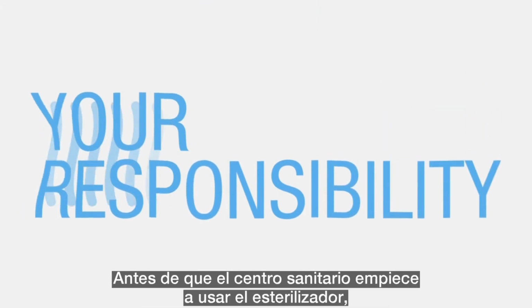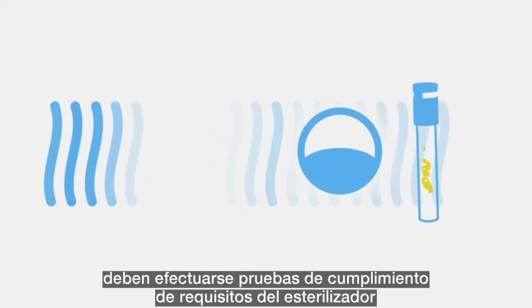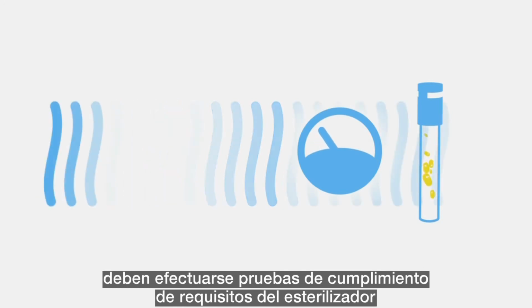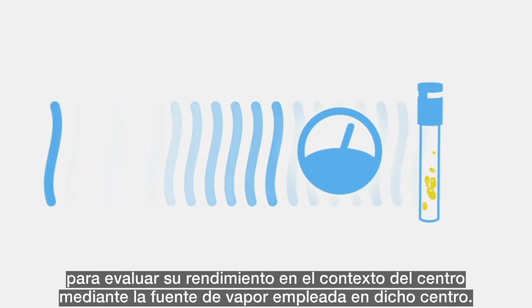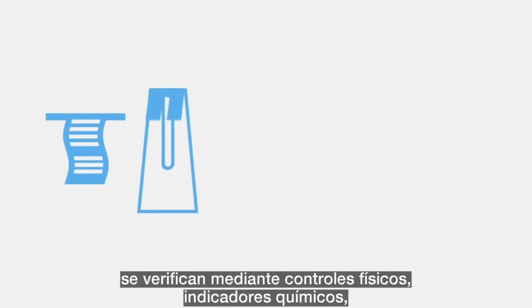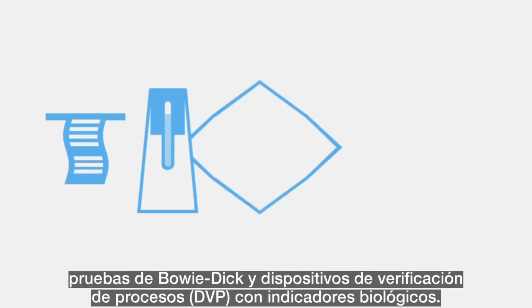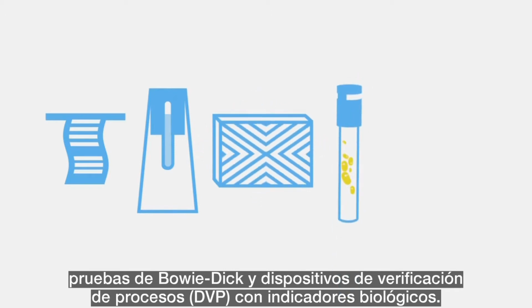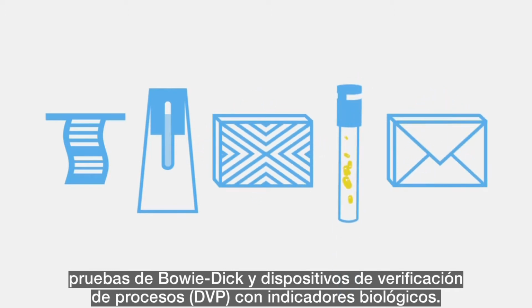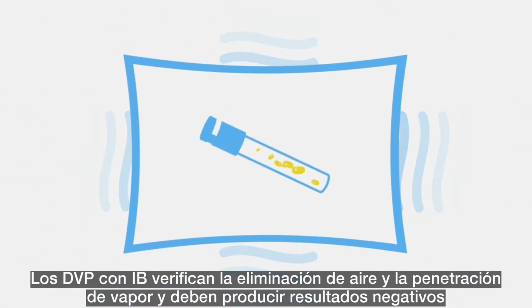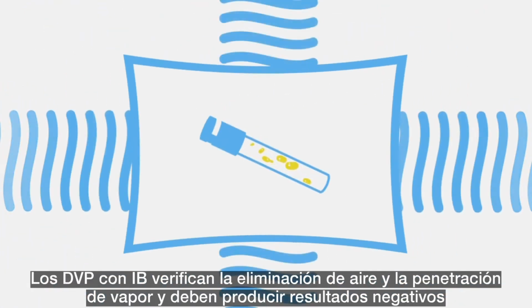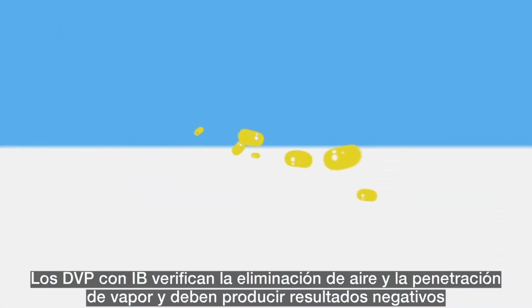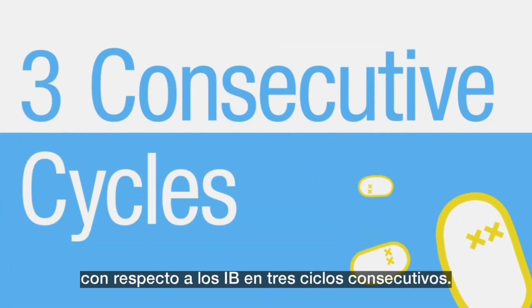Before your facility even puts your sterilizer into use, you must perform sterilizer qualification testing to assess the sterilizer's performance in your environment using your very own steam supply. Sterilizer qualification testing for dynamic air removal sterilizers is performed with physical monitors, chemical indicators, Bowie-Dick tests, and biological indicator process challenge devices, PCDs. The BI-PCDs present a challenge to air removal and steam penetration and must yield negative BI results from 3 consecutive cycles.